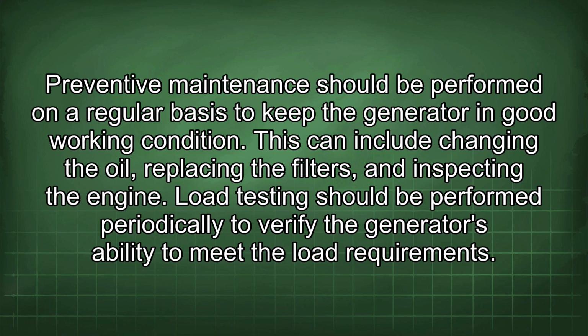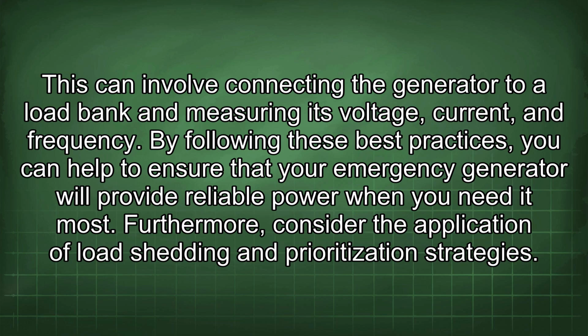This can include changing the oil, replacing the filters, and inspecting the engine. Load testing should be performed periodically to verify the generator's ability to meet the load requirements. This can involve connecting the generator to a load bank and measuring its voltage, current, and frequency. By following these best practices, you can help to ensure that your emergency generator will provide reliable power when you need it most. Furthermore, consider the application of load shedding and prioritization strategies.